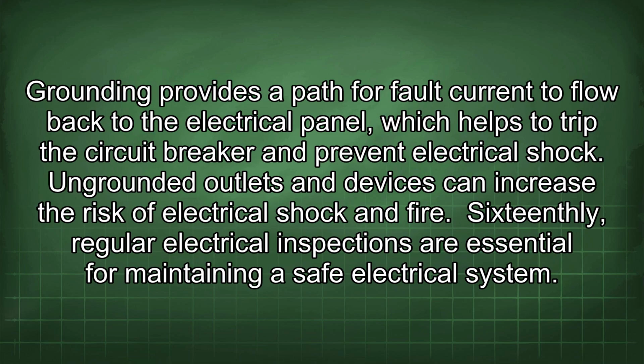Grounding provides a path for fault current to flow back to the electrical panel, which helps to trip the circuit breaker and prevent electrical shock. Ungrounded outlets and devices can increase the risk of electrical shock and fire.